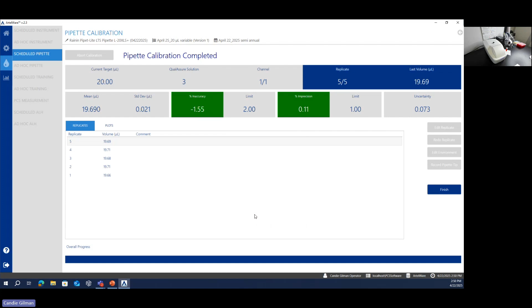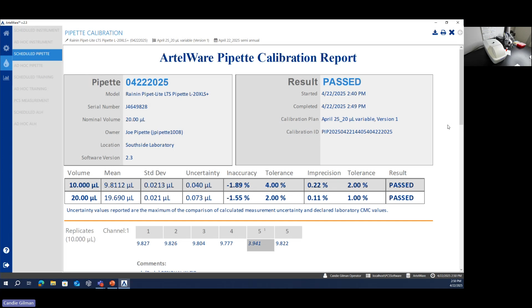So this gives you your initial report. So what do I mean by initial? Remember, this calibration is not completed until it's been reviewed. But let's take a look at the report. All of the information you would expect to see about the pipette, a unique calibration ID, the calibration plan, the date of calibration, everything about the statistics. So you might remember that I had that data point that I did a redo on. So it doesn't get swept under the rug and completely disappear.